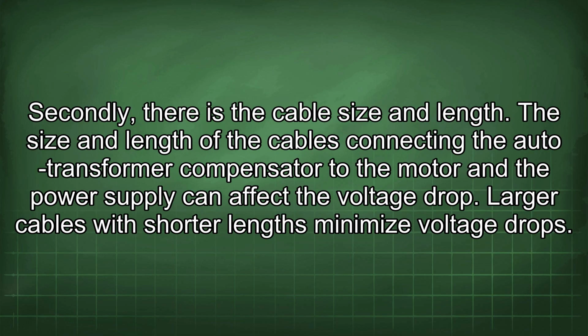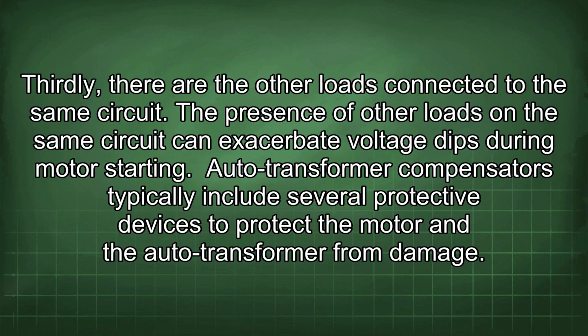Secondly, there is the cable size and length. The size and length of the cables connecting the auto transformer compensator to the motor and the power supply can affect the voltage drop. Larger cables with shorter lengths minimize voltage drops. Thirdly, there are the other loads connected to the same circuit. The presence of other loads on the same circuit can exacerbate voltage dips during motor starting.